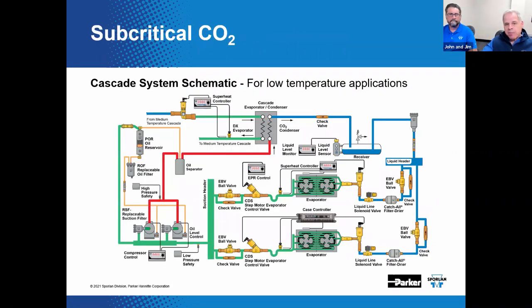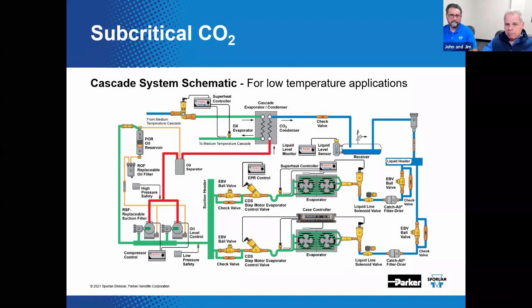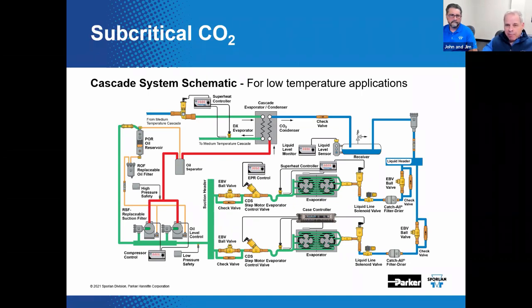this is subcritical cascade DX CO2. Cascade CO2 systems of this type are typically only applied to low temperature refrigeration. This cycle is comparable to the liquid overfeed schematic in that it uses a DX HFC system to cool the CO2 side. The CO2 side really operates pretty much like that typical DX HFC vapor compression refrigeration system that you know.